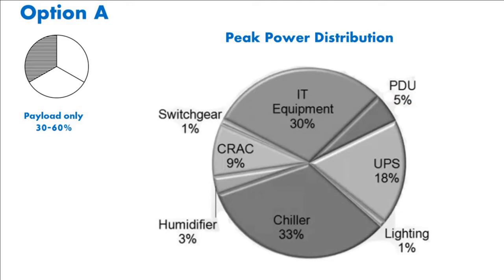From open sources, on the example of calculating the distribution of the total energy supply to a corporate data center in peak mode, we see that the share of IT load is only 30%. In commercial data centers, this figure is closer to 60%. I note that this is a very significant indicator for evaluating investments.